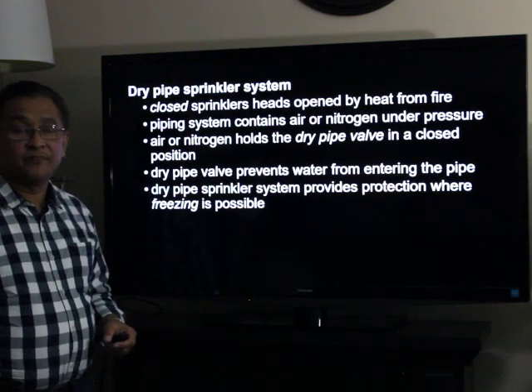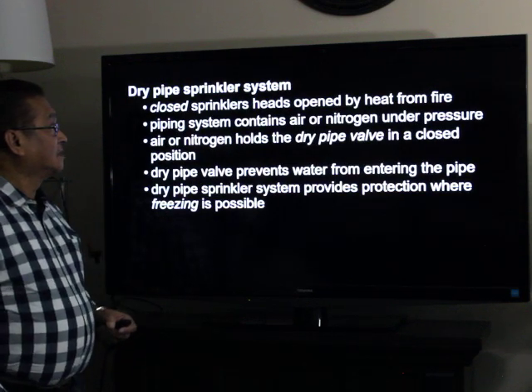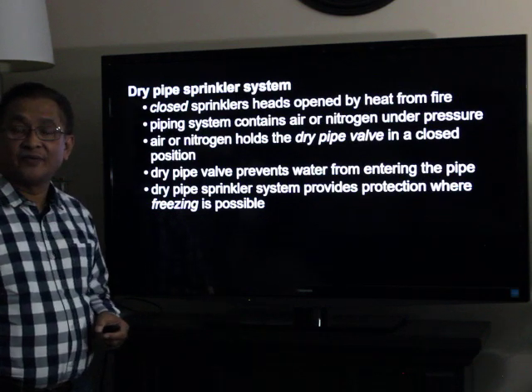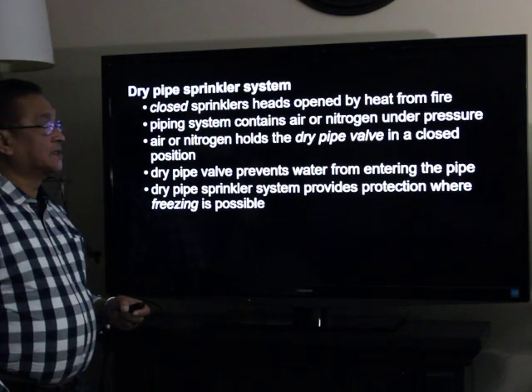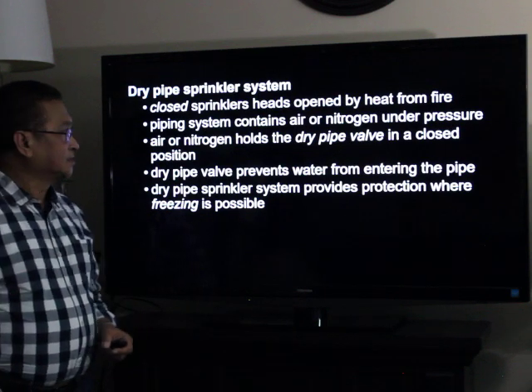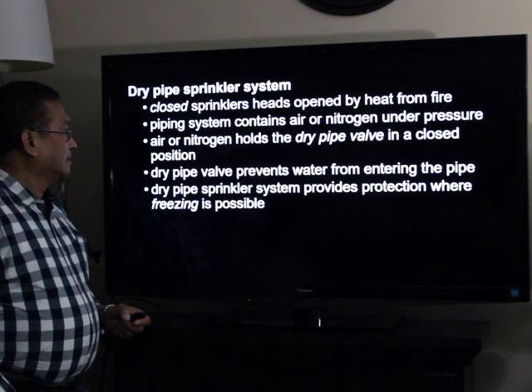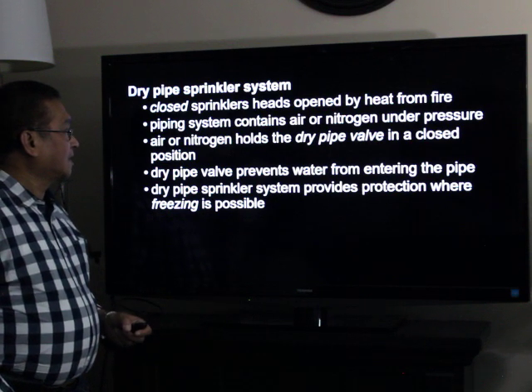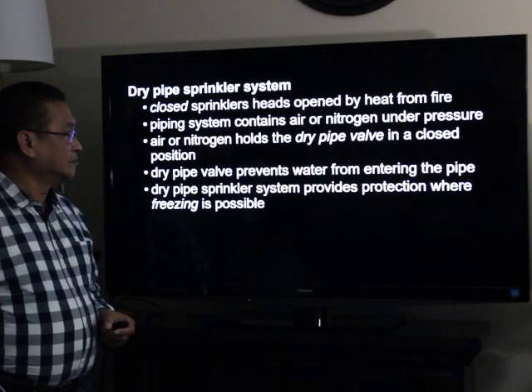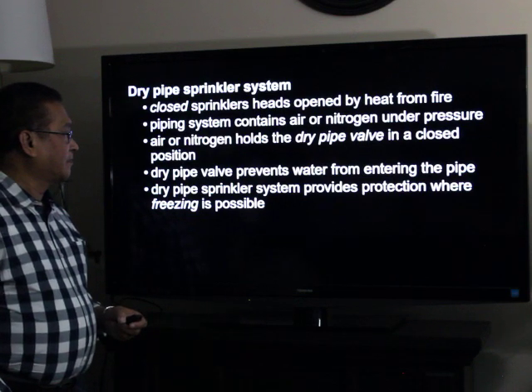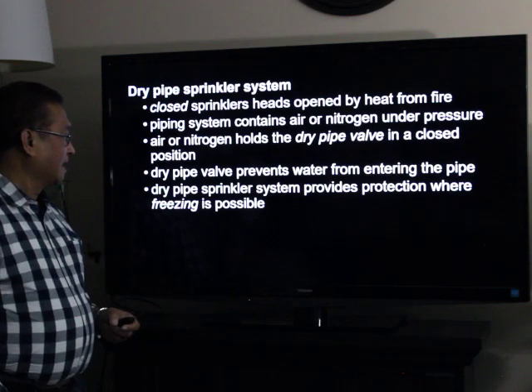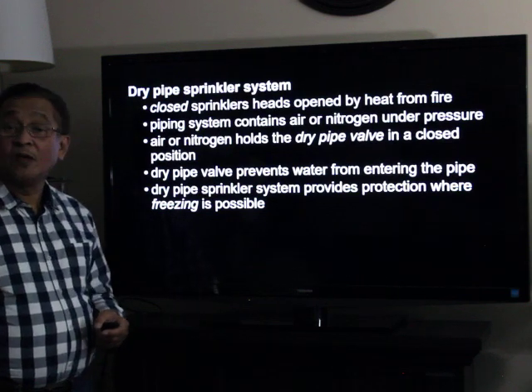In a dry pipe sprinkler system, we have closed sprinkler heads opened by heat from fire. The piping system contains air or nitrogen under pressure. Air or nitrogen holds the dry pipe valve in a closed position. The dry pipe valve prevents water from entering the pipe.